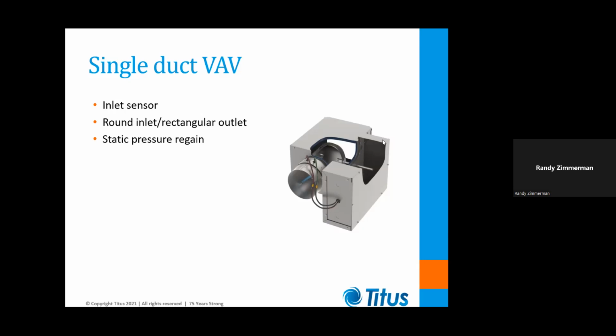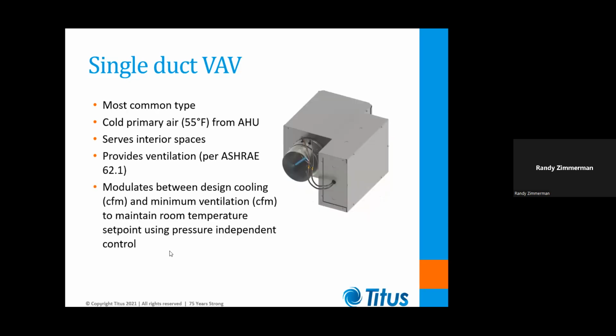Of course, we also know that the round inlet is the most efficient way to deliver air to a room. Like I always say, air is round. You can put it into a rectangular inlet, but then it just goes oval shaped. So we want to have a round inlet. We want to have that rectangular discharge. The rectangular discharge is also the most convenient for connecting our field fabricated duct runouts, where we're going to have our takeoffs for our diffusers and our balancing dampers, and then connect our flex duct and then our diffusers.